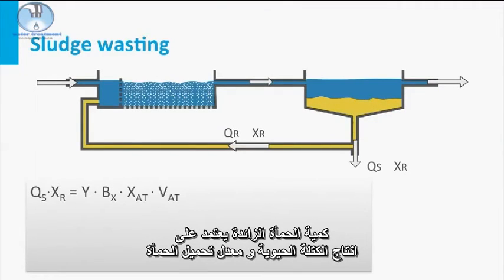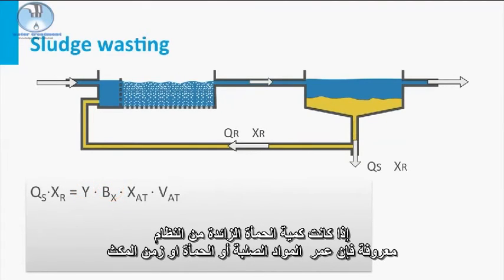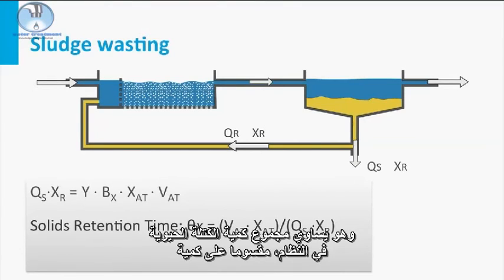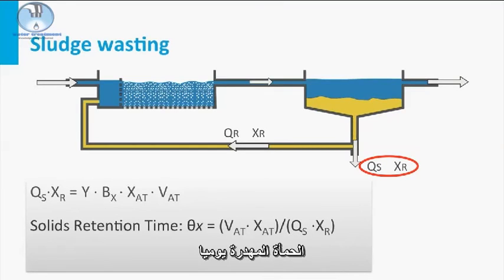The quantity of waste sludge depends on the biomass yield and the sludge loading rate. If the amount of sludge wasted from the system is known, the solids or sludge retention time, or SRT in short, can be calculated. The SRT is the average time sludge stays in the process. It is equal to the total quantity of biomass in the system, divided by the quantity of sludge wasted per day.